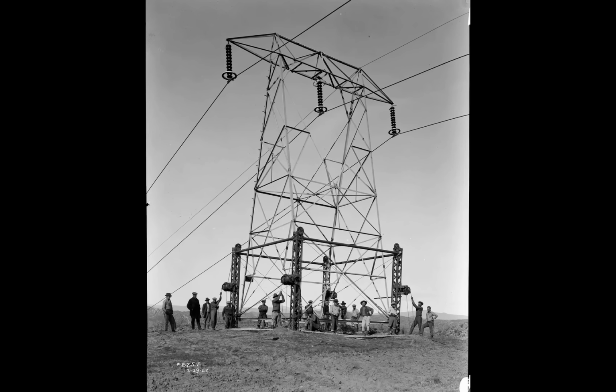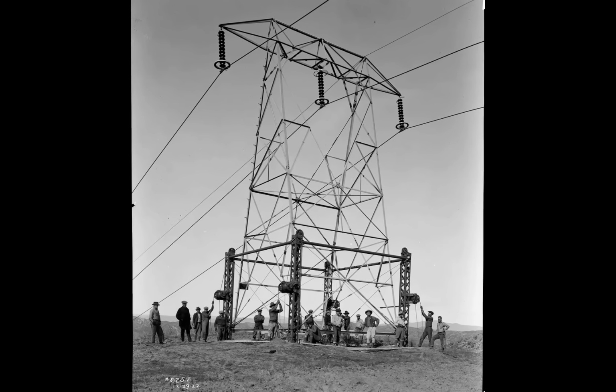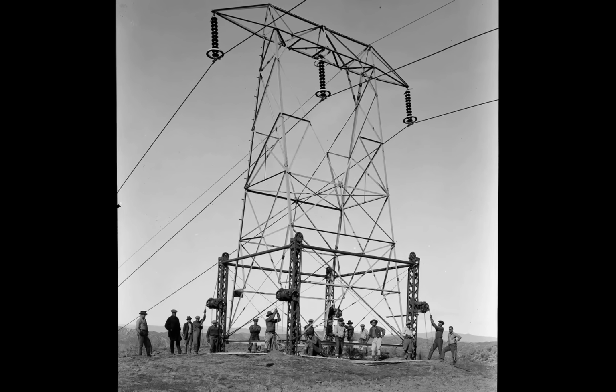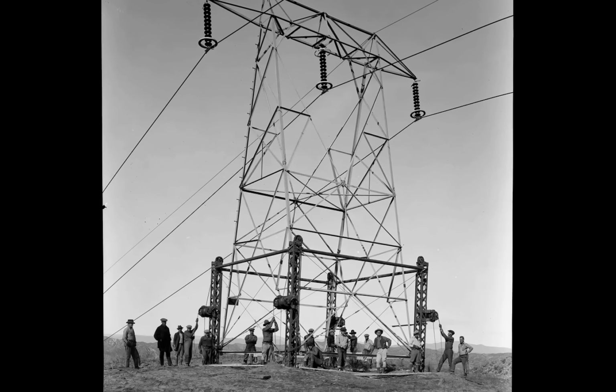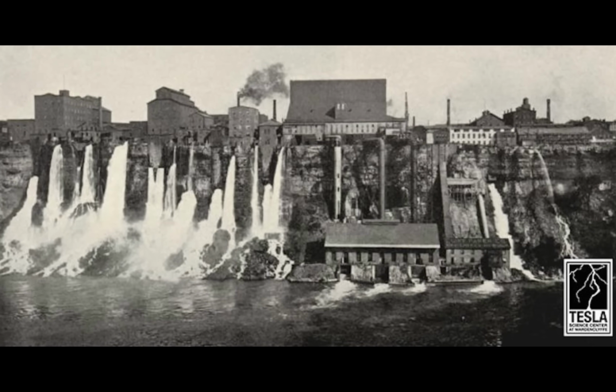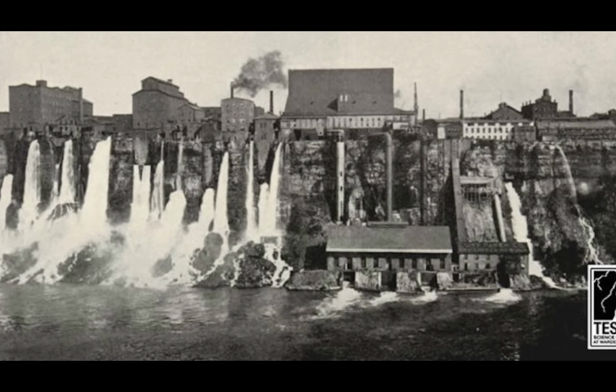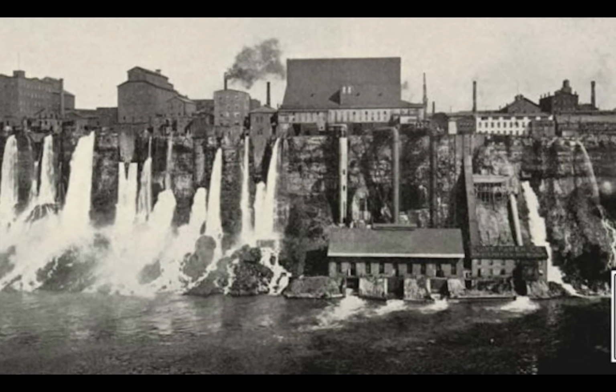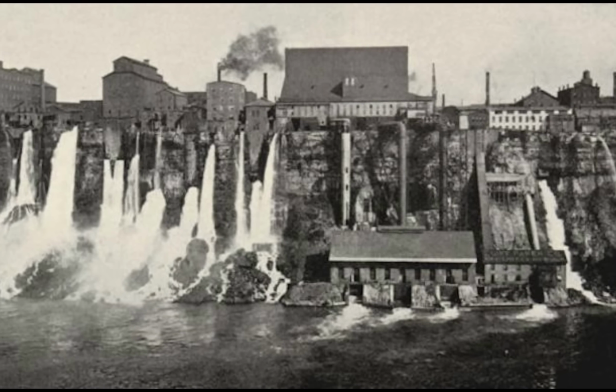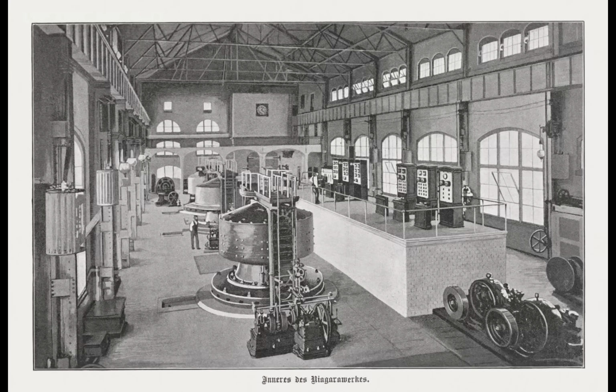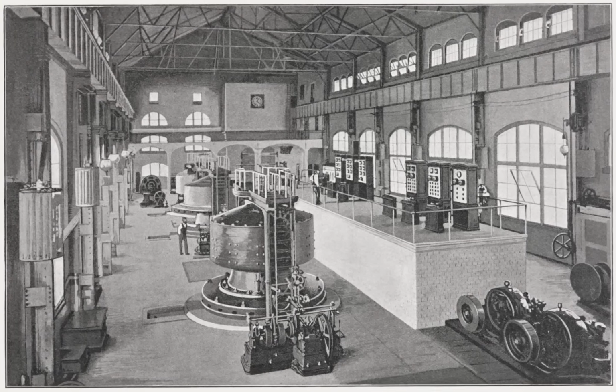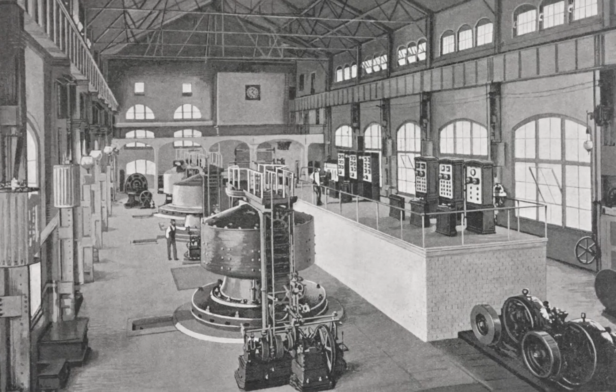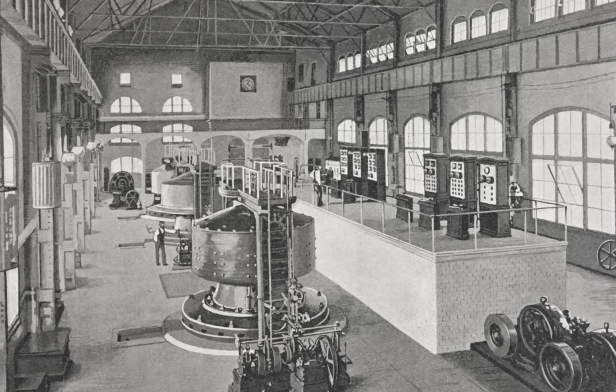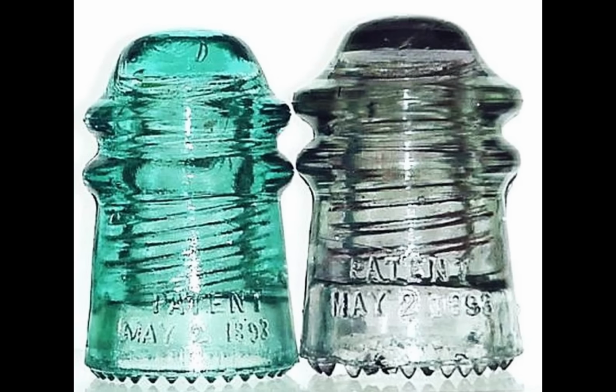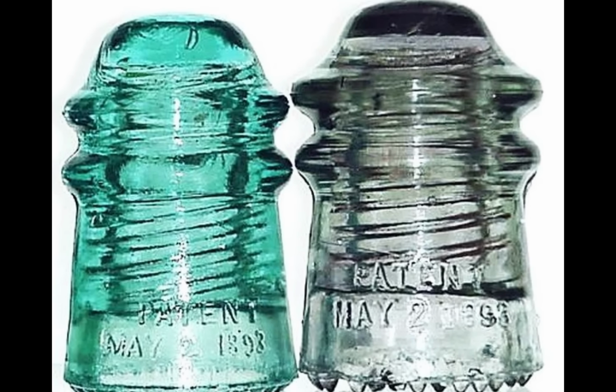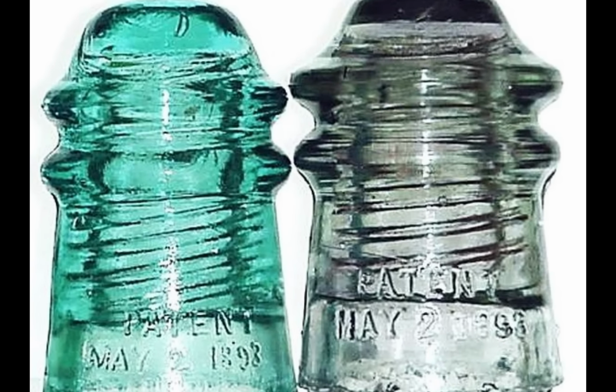Engineers calculated that a 4-part pin insulator rated for 60,000 volts needed a top shelf roughly 16 inches across and weighed more than 30 pounds, all balanced on a 16 to 20-inch pin acting as a lever arm. Under wind load, that lever arm put enormous strain on a single point of failure, the porcelain-to-pin joint. Utility engineers of the era described reaching the limit of the pin-supported type in plain terms, not a design choice, but a wall.